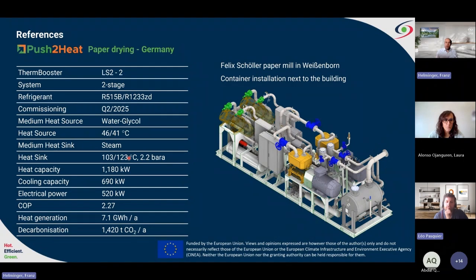Therefore, we decided to go to a two-stage, so that means two heat pumps connected to each other with two different refrigerants. In the low temperature heat pump circuit, we have the R515B refrigerant, and in the high temperature circuit with our compressors, we have the 1233 again as a refrigerant. And yes, we are generating steam. In the CAD model, you can see the screw compressors and the low temperature cycle. On the right-hand side, you can see our compressors with the electrical motors and the steam generator. We expect around 2.27 or 2.3 COP with a capacity of nearly 1.2 megawatts.